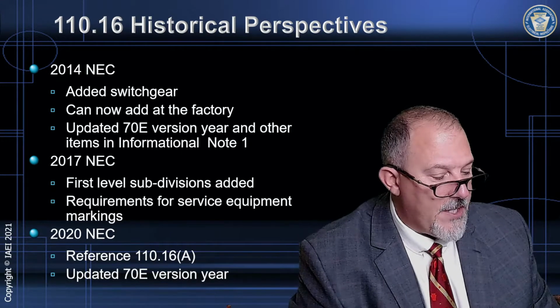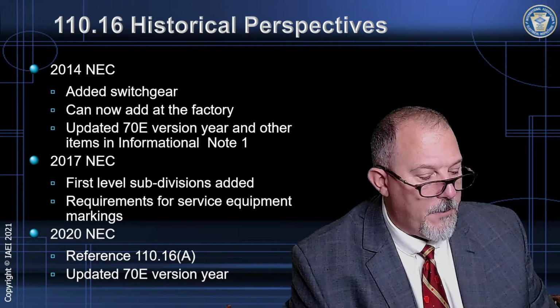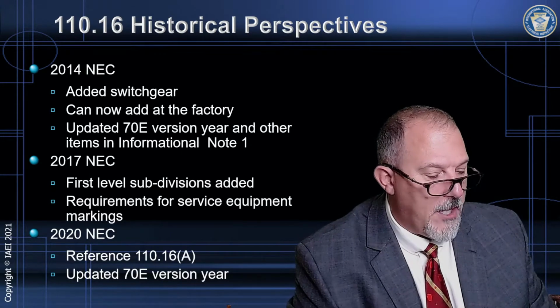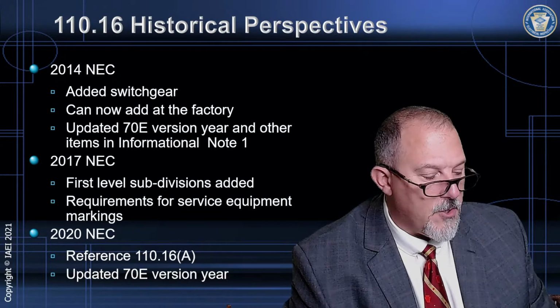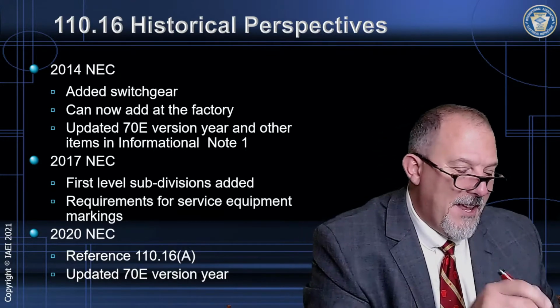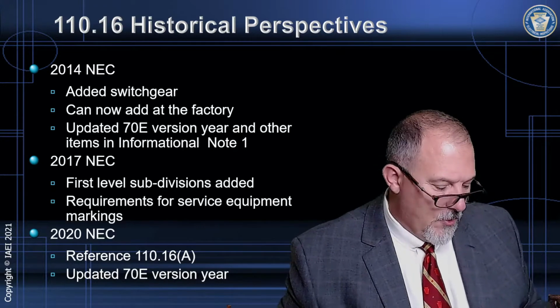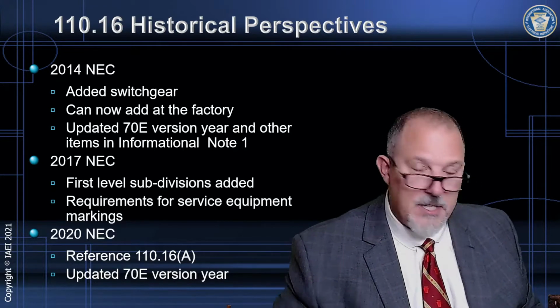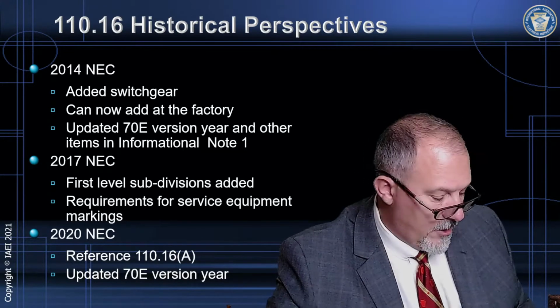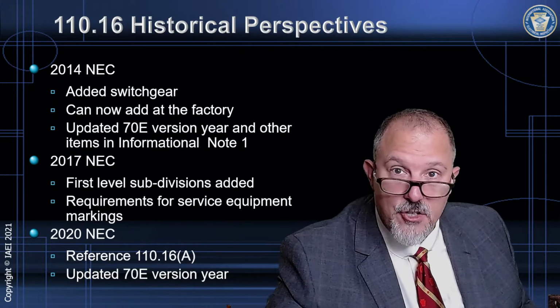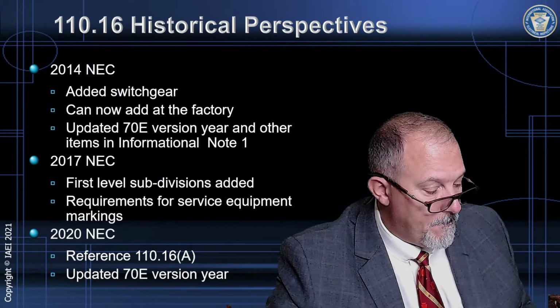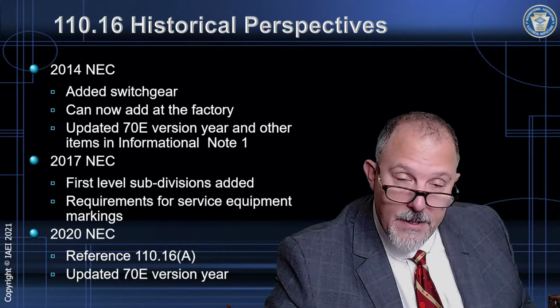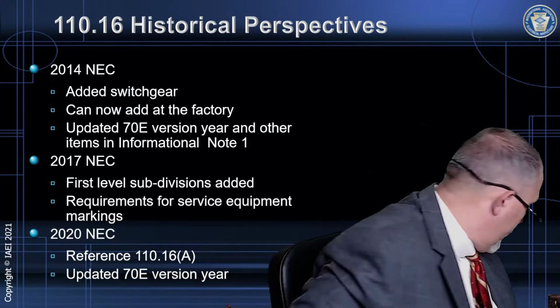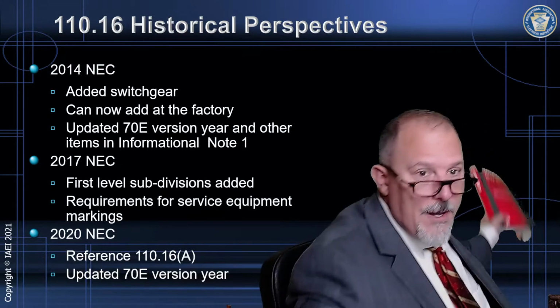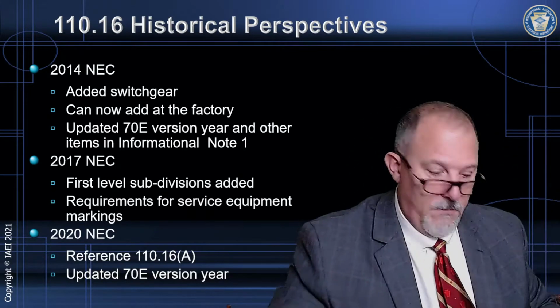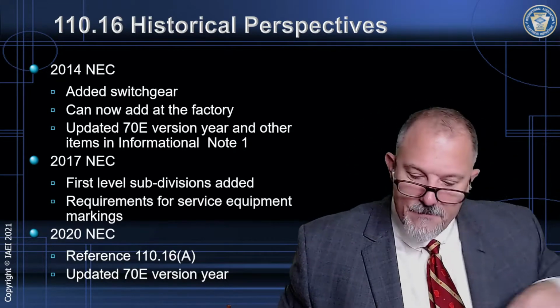But it says the arc flash hazard markings shall meet the requirements in 110.21(B) and shall be located so as to clearly be visible to qualified persons, blah, blah, blah. So they put the reference to 110.21(B), which is the field applied hazard markings, but they should have also put the reference to 110.21(A) if the manufacturer puts them on. We'll see if that changed. Do you know why? Because we're going to grab the 17. And I'm going to leave this one open because I just noticed that.